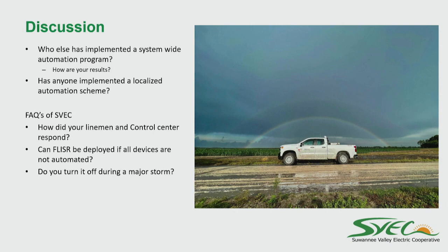Our control center staff, at first, when we first put these devices in the field before FLISR was live, some of the questions were: do I have to do these switching opens and closes? Yeah, hey, we've got all the data there, we've got these devices sitting there, you have to open, close, move load around, get people back on. I think the biggest thing to them was we always waited for the linemen to tell us what they saw. Well, now SCADA is telling you what it's seeing.